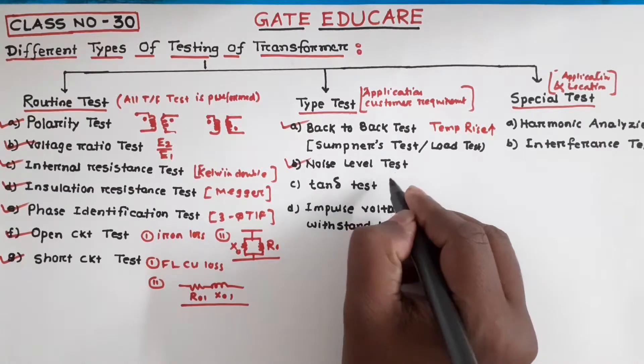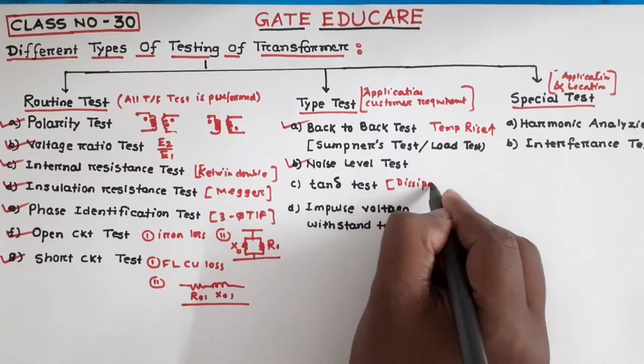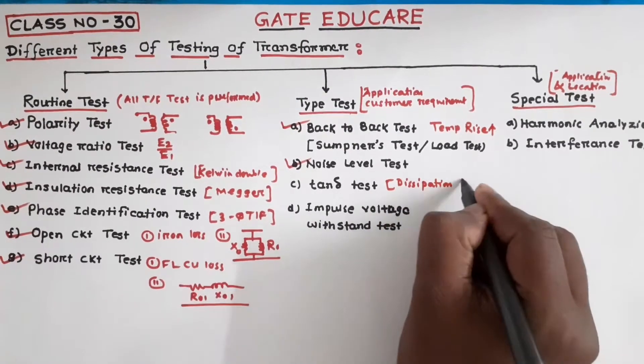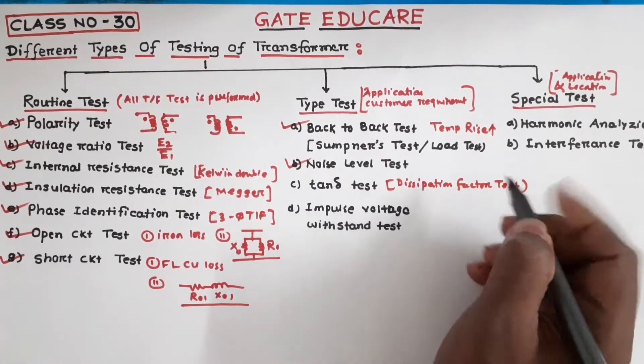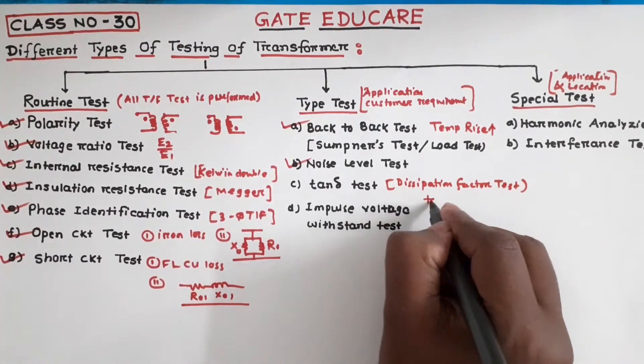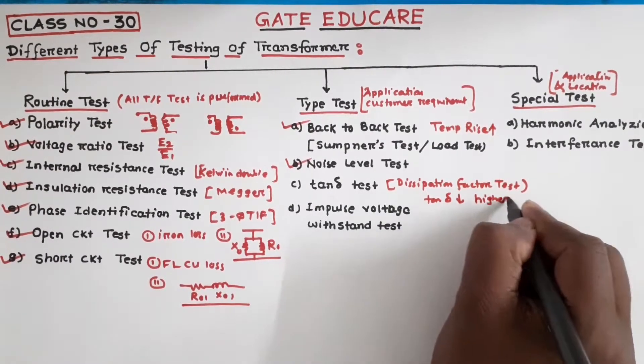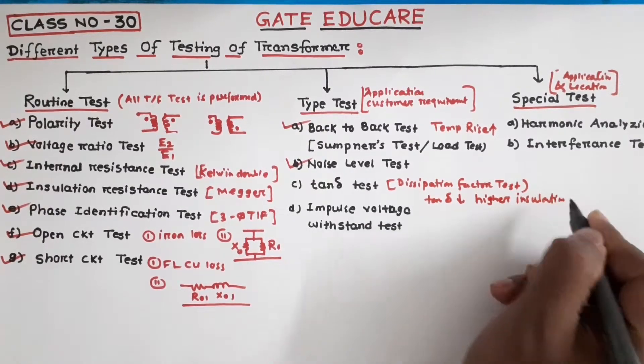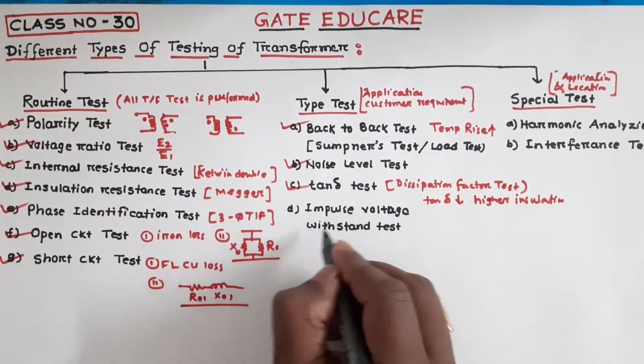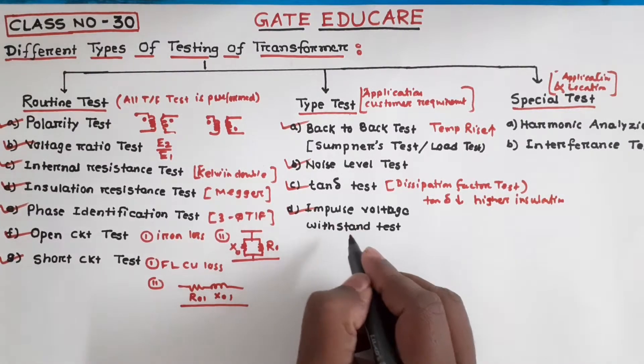Tan delta test: the tan delta test is generally a measure of insulation condition. It is also called the dissipation factor test. The lower the tan delta value, the higher the quality of the insulation. Next, the impulse voltage withstand test: how much impulse voltage the transformer can withstand is determined with this test.